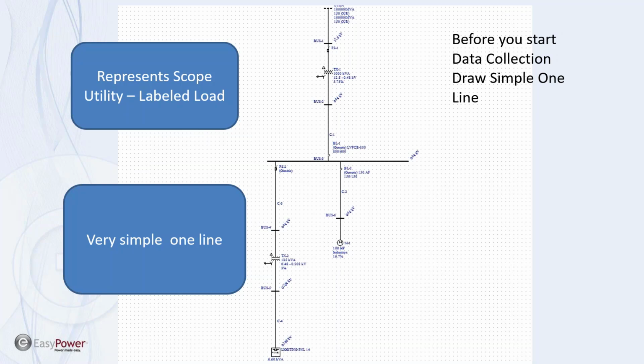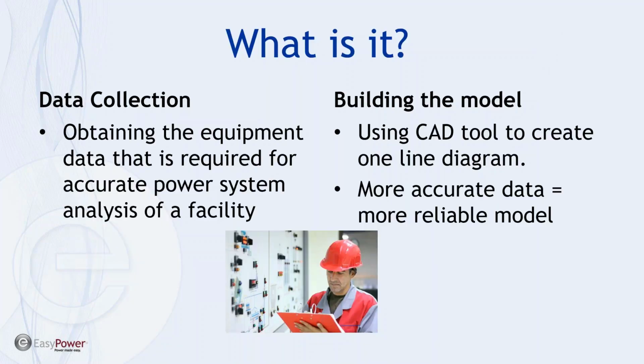So again, playing with the tools a little bit, asking questions about the mechanics is well worth the time spent before you start the data collection. Data collection is actually recording the equipment data that's required for the accurate power system modeling and analysis of the facility. And you'll see as we get into the estimated time, normally, unless you have a lot of protective devices that need coordination, the data collection process and building the one-line model represent about 50% of the man hours, or people hours, that it requires to complete a study.